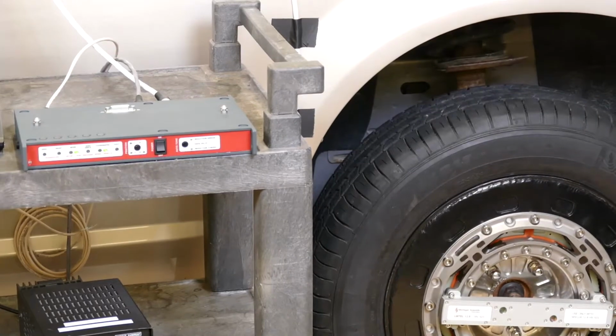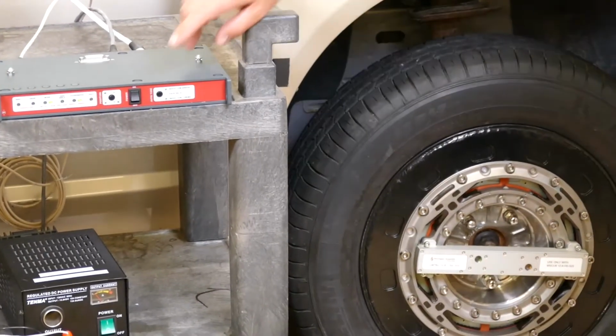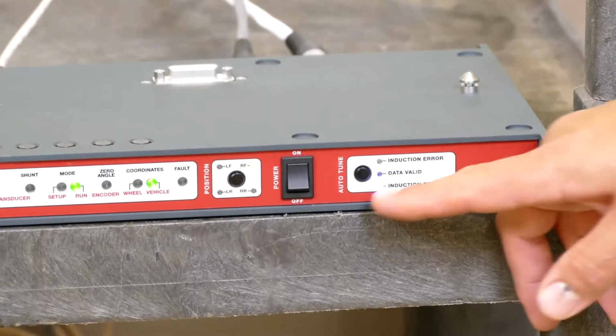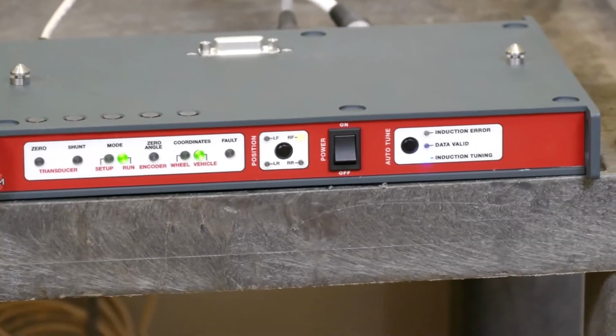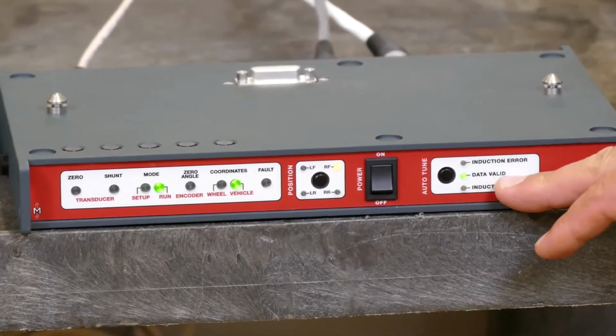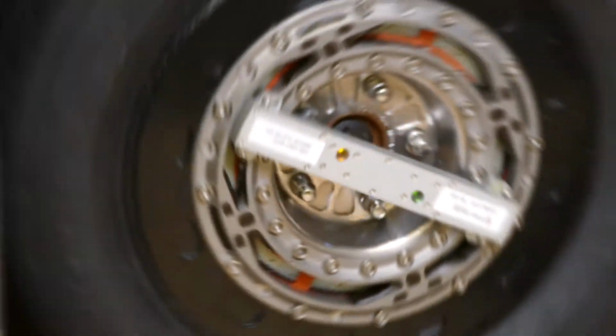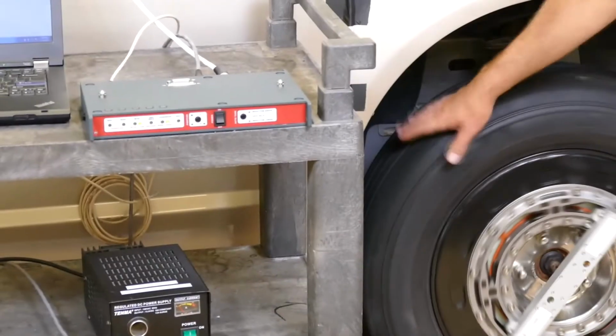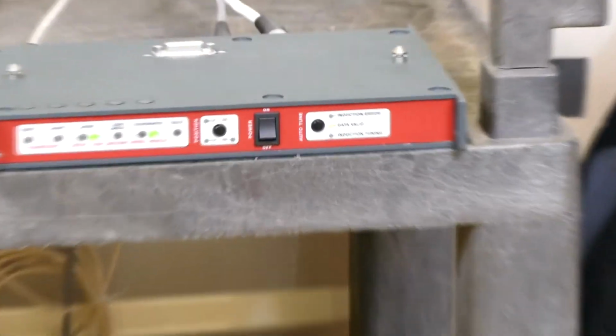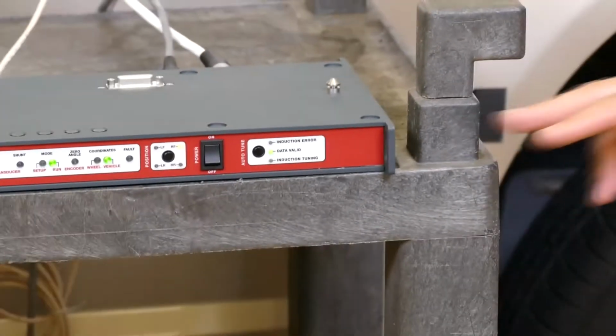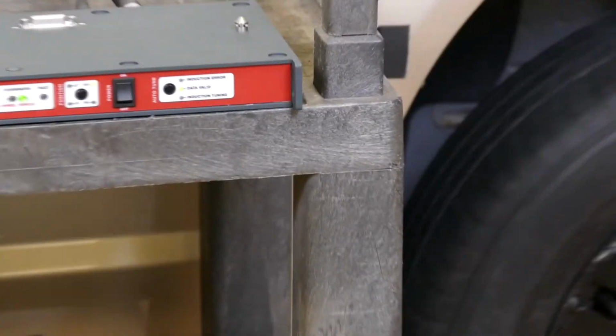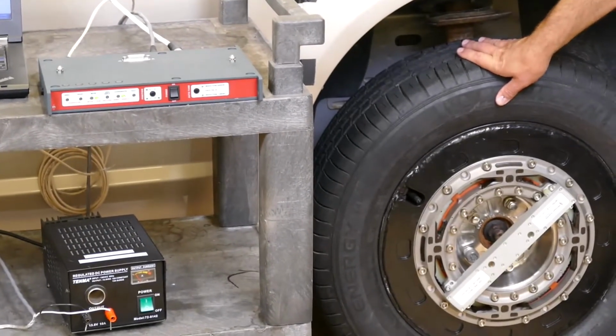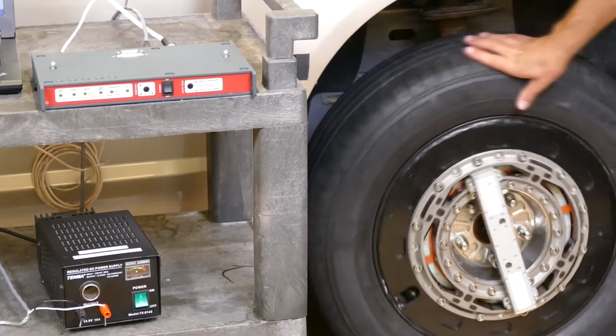If we rotate the wheel a little, we see some faults. That means that we need to do an auto tune on the telemetry, or on the induction power. To do that, you simply press the button here. The blue light indicates that we're in the tuning process, so we have to wait for that to complete. We'll finish the tuning process, and now it says data valid light. And if we rotate the wheel, we should rotate the wheel the entire revolution and not get any fault lights, and that's the case. If you rotate it and you get one induction error as you rotate, then you should stop at that spot. We get the error and do the retune. In this case, we've got no errors.